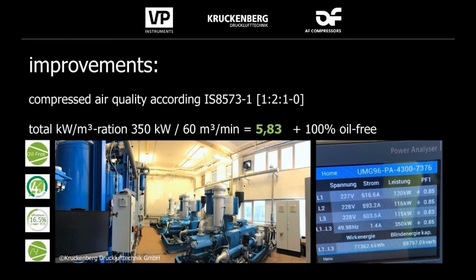And the customer is really happy about this because he can also prove these values and can follow up and monitor the system. And he's going for decentralized measurements for the consumption, for the production, to keep track of upcoming new leakages, because leakage optimization is a permanent battlefield. And there's no excuse for not monitoring or taking action there. It should be monitored with decentralized multiple flow meters for production lines, production rooms, halls, or individual lines. And they can tell you for a very limited amount, or for a nice saving, when to take action in the system, and very quickly, because in the past, they only could see the complete consumption.